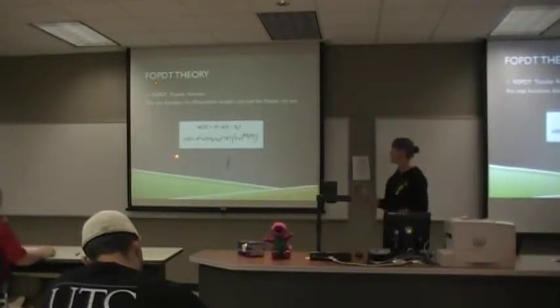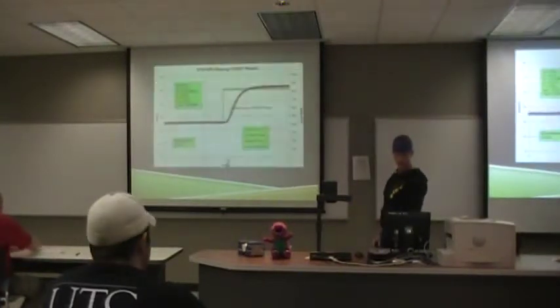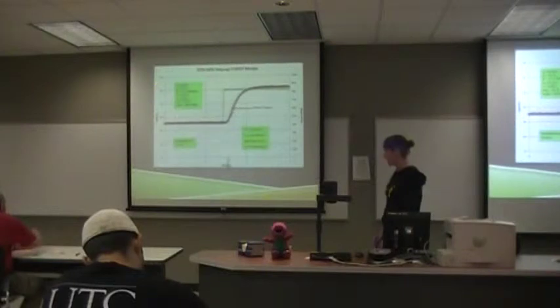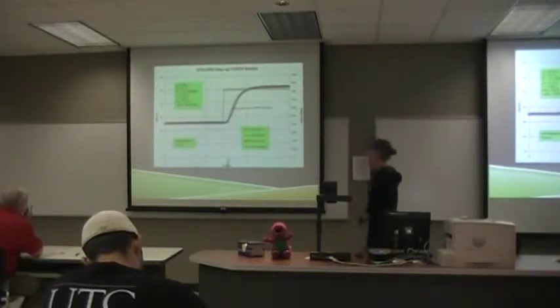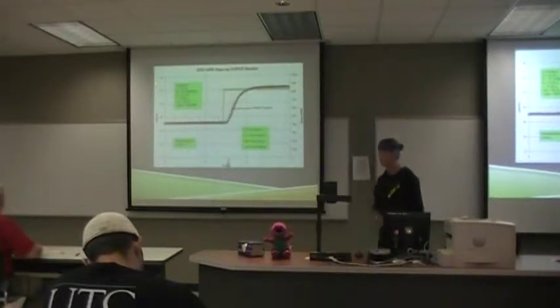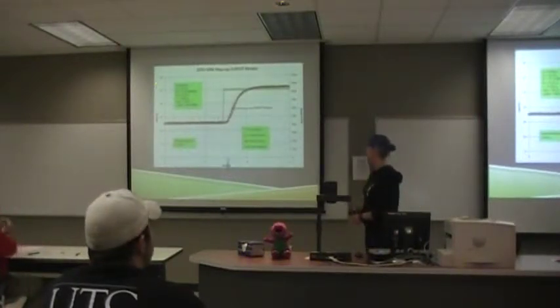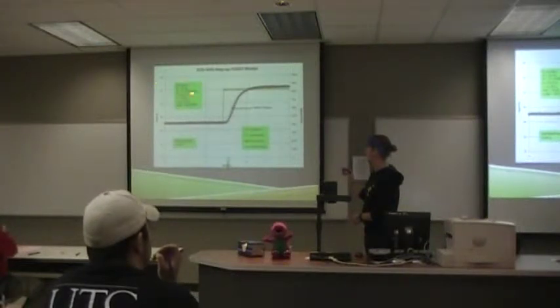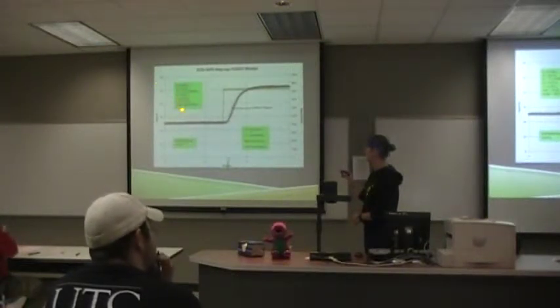For our first order plus dead time model, this is the manipulated variable, the input. This is our output. These are mathematical representations of the outputs. Here's the model along with the experimental data placed on top of it. We adjusted the model to match the experimental data to give us these parameters right here. The input and output were placed in there for the model, and then K, T0, and tau were adjusted to match them.